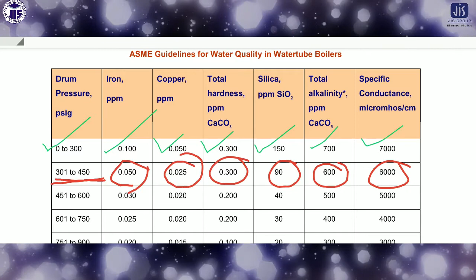So all these are related. If we change the pressure here, from 301 to 450, then all the concentrations, like iron, copper, total hardness, and silica, will change. So this guideline is very important for maintaining the boiler water quality parameters, because with the drum pressure all the other things are very related to each other. In this way we have to maintain the boiler water quality parameters.